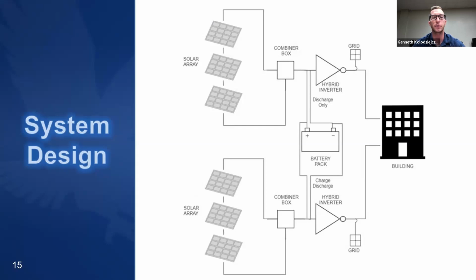A challenge we faced was these power surges occur in relatively short periods of time, and the number of nighttime inverters cannot discharge the stored energy at a fast enough rate. Instead of implementing more inverters into the nighttime system, the daytime system inverters will also be connected to the battery bank to discharge only. This will ensure the stored energy is discharged in the short periods of time high power surges occur.